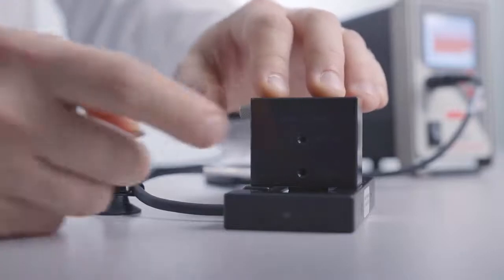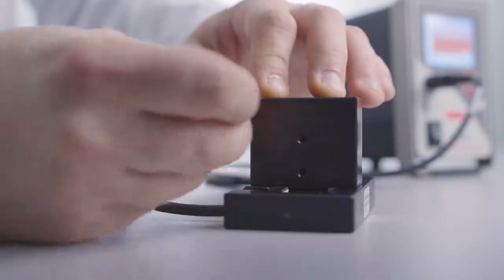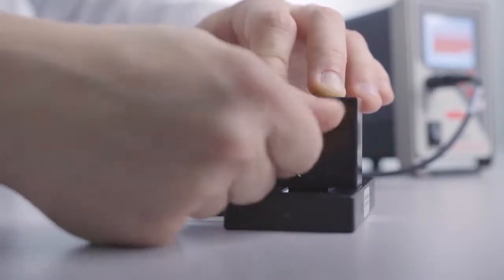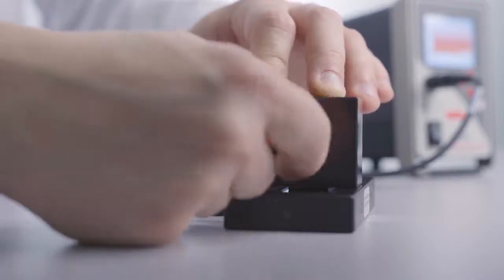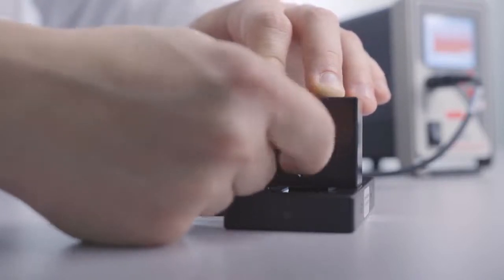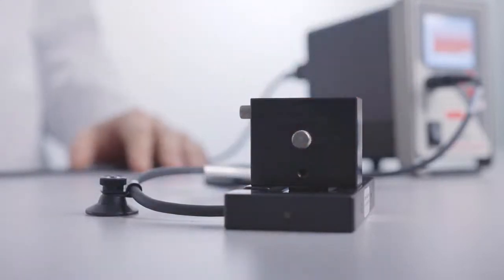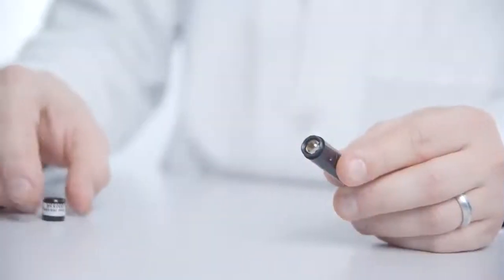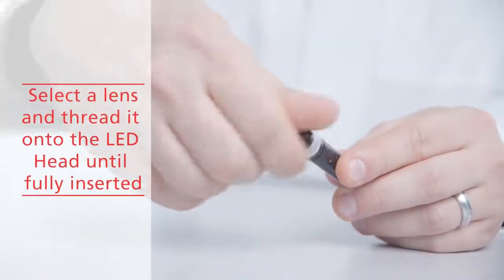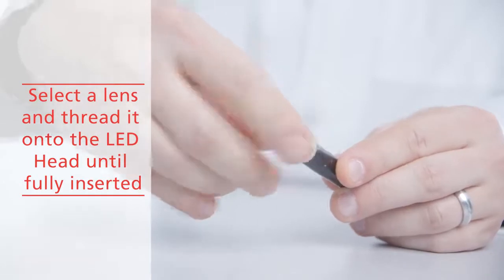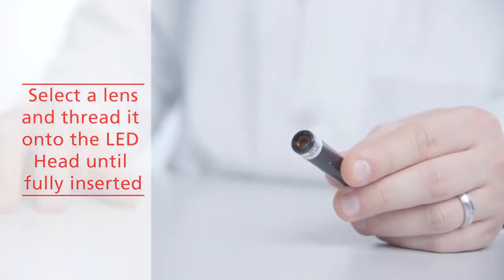Insert the provided thumb screw into the appropriate setting on the beam positioning kit block, matching the engraved dimension on the block to the selected focusing lens size. One side is used for the irradiance calibration while the other is used for the optical power calibration. Select your desired lens and thread it onto the LED head until fully inserted. No gaps should be visible between the lens and the LED head.